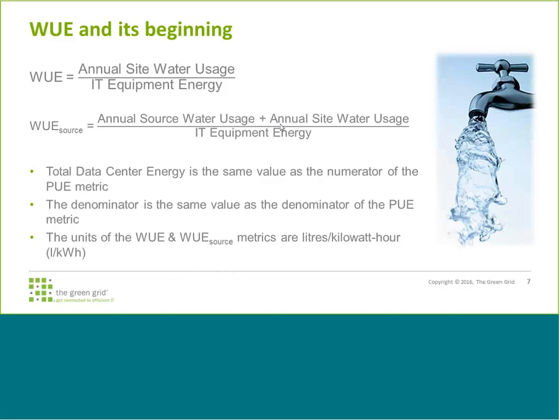Yeah, I'm probably going to goof up the source one, because the easy one is just looking at the total amount of water usage that comes into the building, and then you're dividing it, much like in PUE, by the IT equipment energy. So what we're looking at is very simply how much water, whether it's in liters or gallons, liters being much more universally understood these days, per kilowatt. So we keep everything in a standard format, or megaliters per megawatt if you want. It's up to you, but the number comes out the same. And the goal, of course, is much like CUE and unlike PUE.